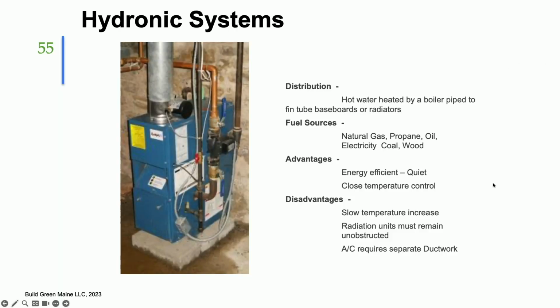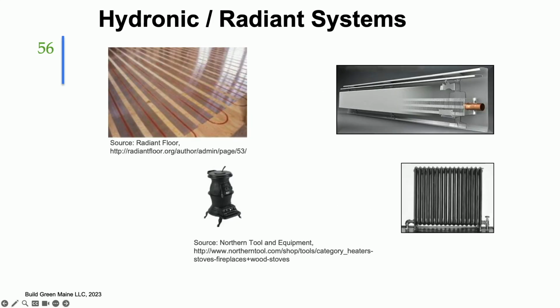If you want to add cooling with a forced hot water baseboard boiler system, you have to add ductwork. You can't run cooling lines through hydronic baseboard, so you still need ductwork.